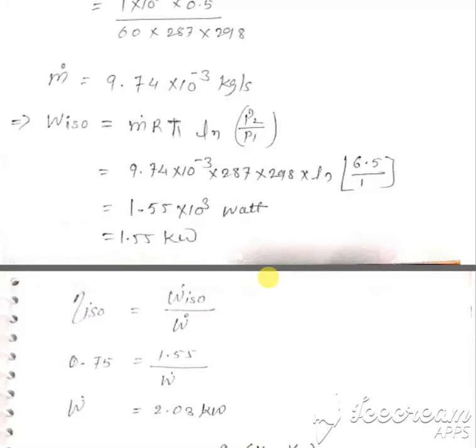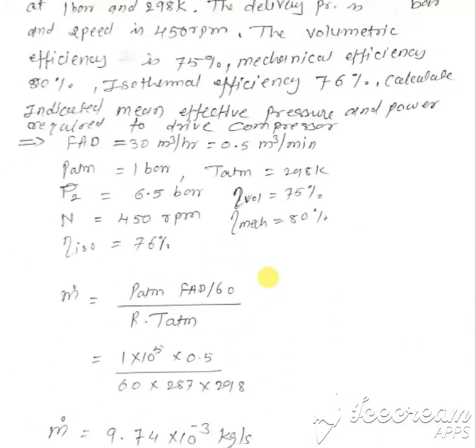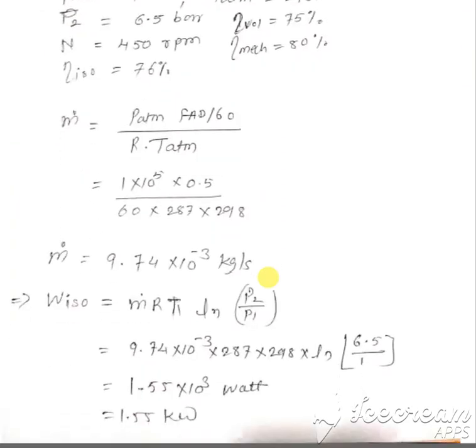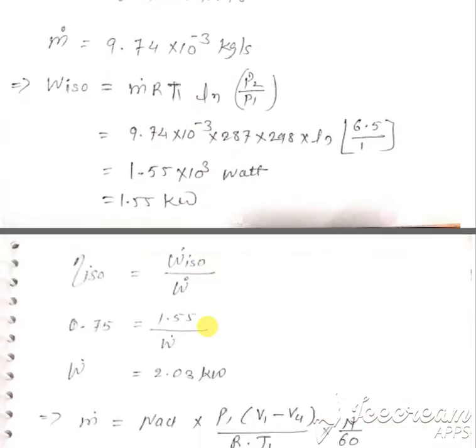In this problem, isothermal efficiency is given, but the value of small n — the index of compression and expansion — is not given. Therefore, we cannot use W-dot = n/(n−1) × M × R × T1 × [(P2/P1)^((n−1)/n) − 1]. Instead, since isothermal efficiency = W_iso / W_poly, we calculate isothermal power: W-dot_iso = M-dot × R × T1 × ln(P2/P1). Then, from isothermal efficiency = W_iso / W-dot, we calculate W-dot, the polytropic power.